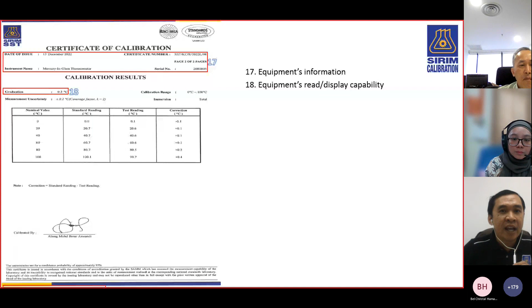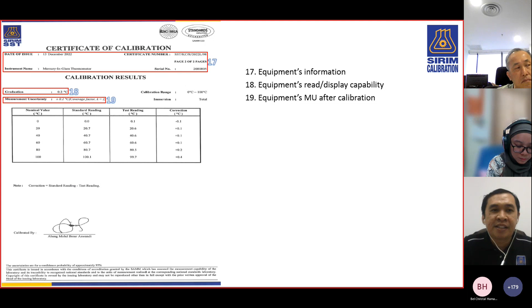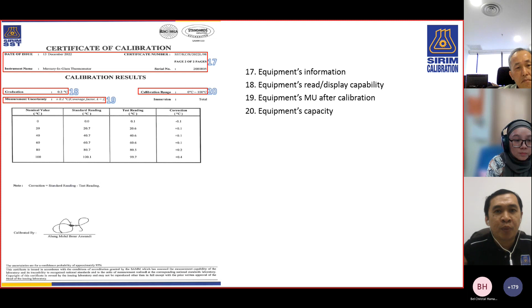Thus, it is not a valid calibration certificate. So this one you need to check as well. For those who are sending the equipment for calibration, you must check whether this laboratory stated this in your calibration certificate. Okay. And of course, the calibration range, at what range we calibrate, and the type of your equipment.